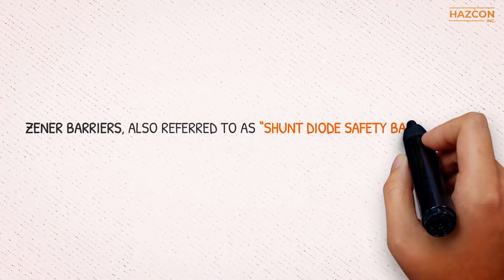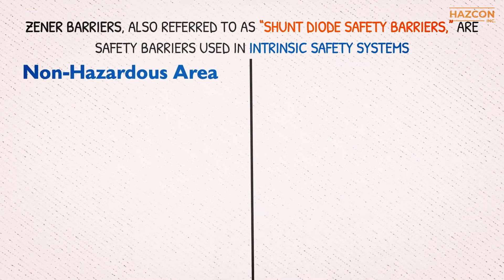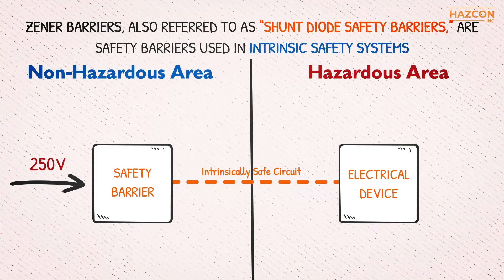Zener barriers, also referred to as shunt diode safety barriers, are safety barriers used in intrinsic safety systems to provide protection for certain electrical devices by limiting the energy going to the hazardous areas.